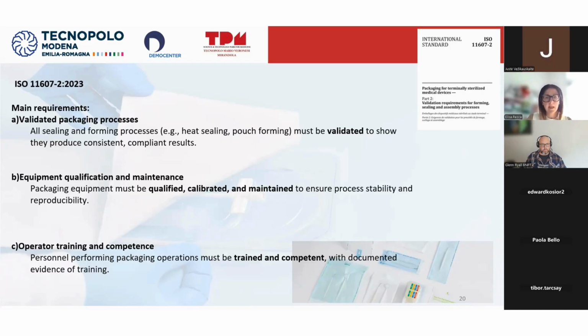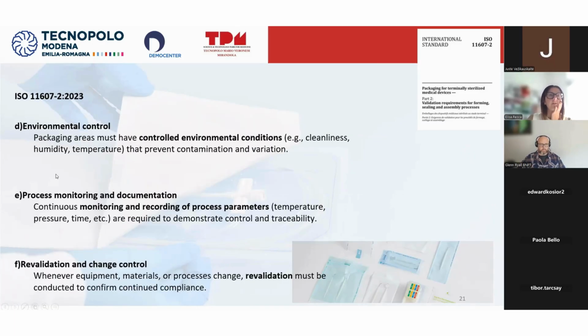And the operator training and competence. Personnel performing packaging operations must be trained and competent, with documented evidence of training. There is also environmental control: the packaging area must have controlled environmental conditions that prevent contamination and variation. Process monitoring and documentation: continuous monitoring and recording of process parameters are required to demonstrate control and traceability. And the revalidation and change control: whenever equipment, materials, or processes change, revalidation must be conducted to confirm continued compliance.